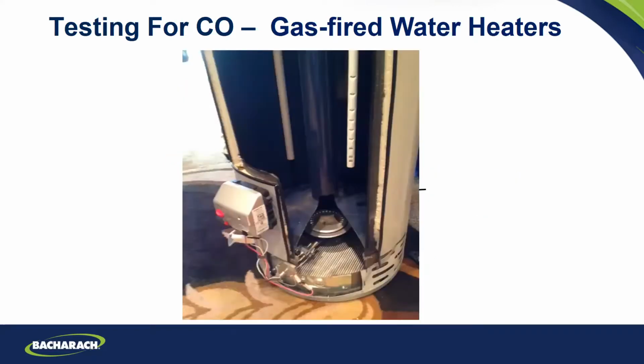A lot of times these burners in a water heater just get dirty. They get a lot of soot because of how a water heater works. This is your burner here. It has a circle of flames, heats up and goes through this tube, and there's a diverter in there, a piece of twisted metal that slows those gases down. The water comes in here, gets heated up, and goes back up.